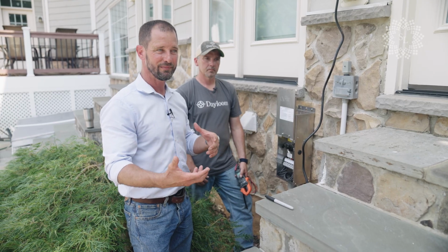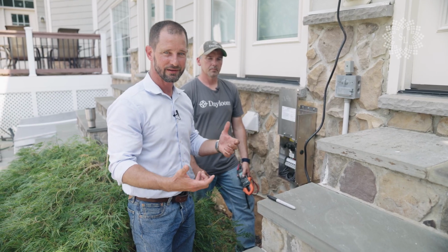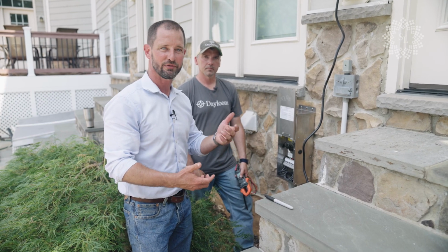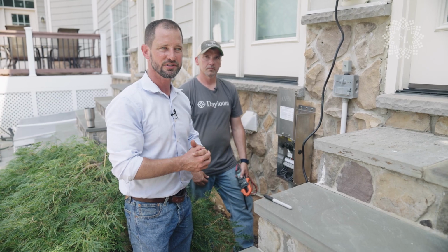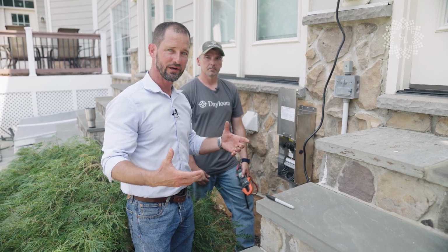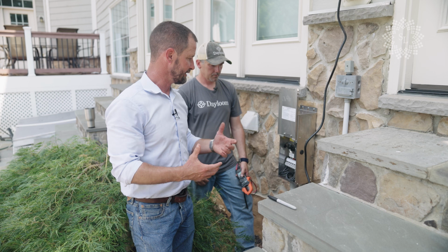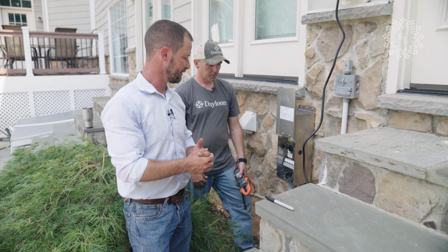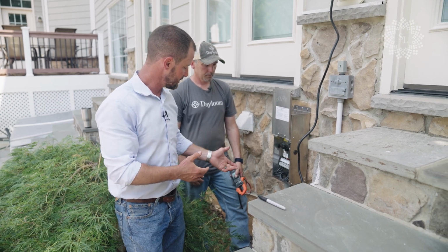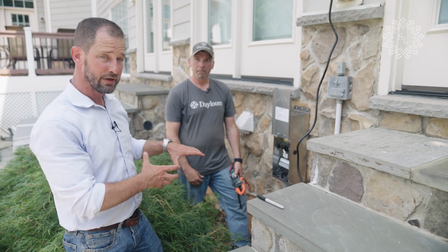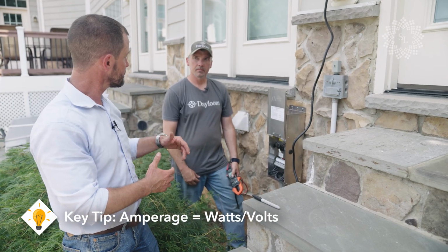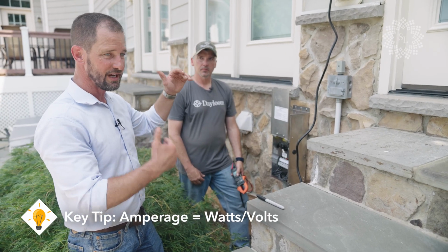So technically it might work, but then 2 months go by and all of a sudden it starts tripping—you're just putting a lot of pressure on it. So we want to make sure we overbuild the capacity. On this, we put in a 600 watt transformer, larger than we needed. Josh is going to show you how to look at the amperage—amperage is watts divided by volts.